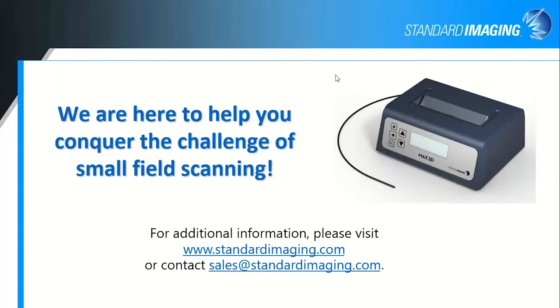Below what energy would you start getting energy dependence? As long as you're in the megavoltage range, you'll be fine. Lower energies, we've had a little bit of investigation with some kilovoltage energies, and there are a couple of mechanisms there. One is the water equivalency of the PMMA or of the scintillator, and I don't remember the threshold below which that starts to show up. But any of your megavoltage beams, you're just fine.